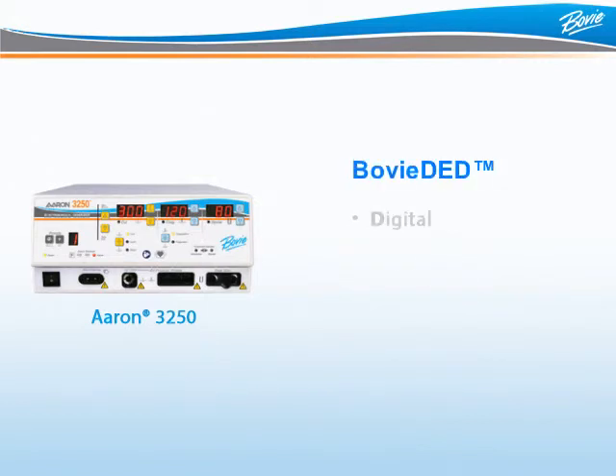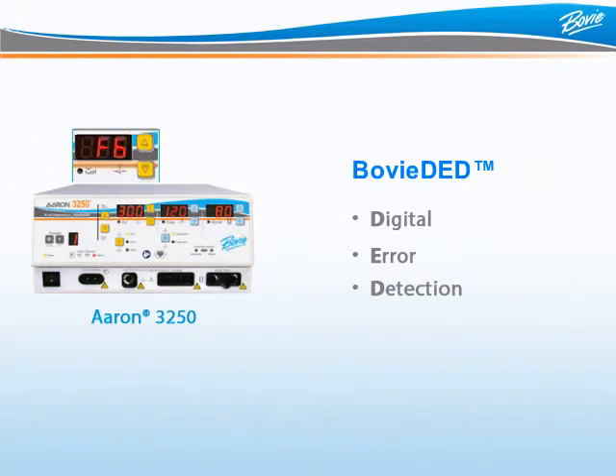Bovie has also developed Digital Error Detection. This means unsurpassed safety for the patient, surgeon, and staff. Bovie DED monitors all functions of the unit to ensure the Aaron 3250 delivers proper top-notch performance. At the sign of any problem, the machine instantly disables the output and an error code is displayed.